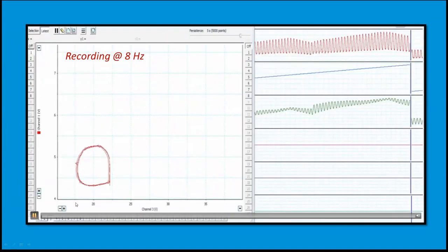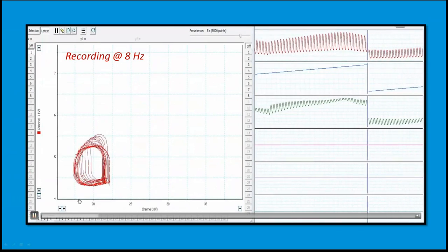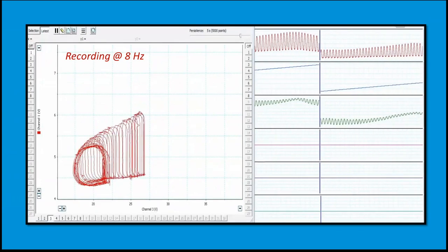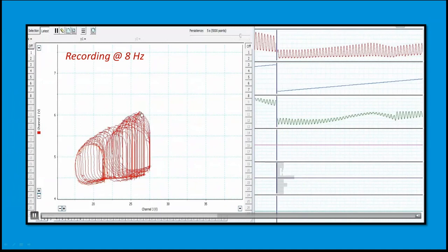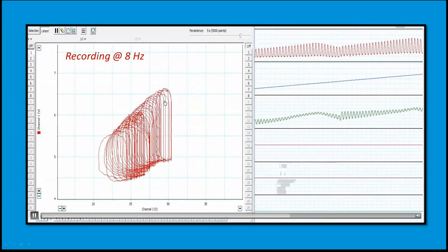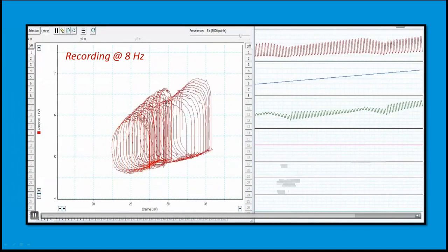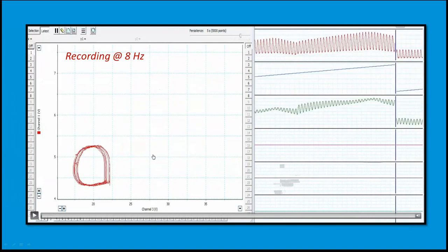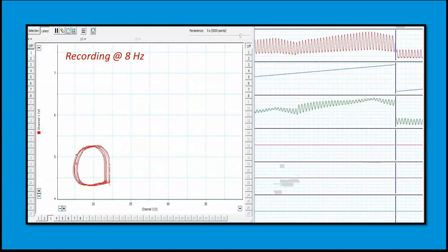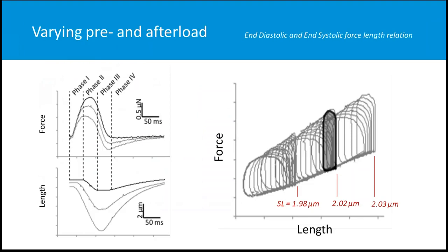One more time, but now at 8 Hertz. You see, speed is not really an issue here anymore. We have a slightly different protocol again where we increase and then slowly decrease the afterload. If you observe this closely, you'll see there is hysteresis. That's how you can do it. You can quickly cycle through different frequencies. Everything is set up. You finish one frequency, you set up the next frequency, and off you go.